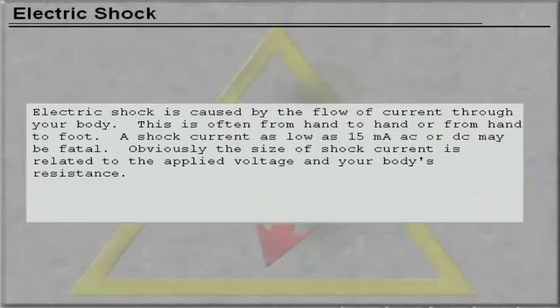Electric shock is caused by the flow of current through your body. This is often from hand to hand or from hand to foot. A shock current as low as 15 mA AC or DC may be fatal. Obviously, the size of the shock current is related to the applied voltage and your body's resistance. Unfortunately, your body's resistance goes down as applied voltage goes up. This means that the shock current is further increased at high voltages.